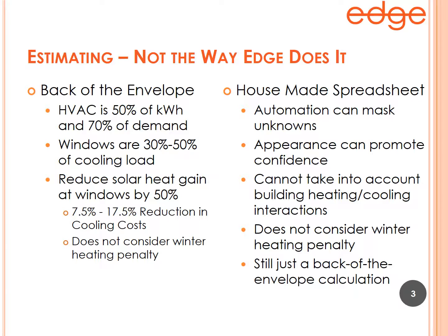A spreadsheet won't take that into account. It also won't consider the winter heating penalty — that is, when you add film to reduce heat in the summer, in most cases you also reduce the free heat you would get in the winter, and a spreadsheet cannot calculate that heating penalty.